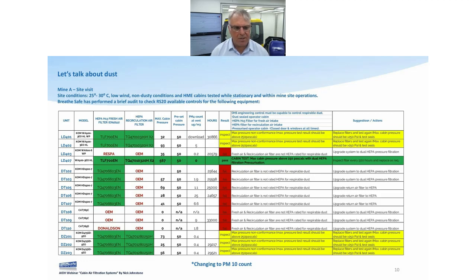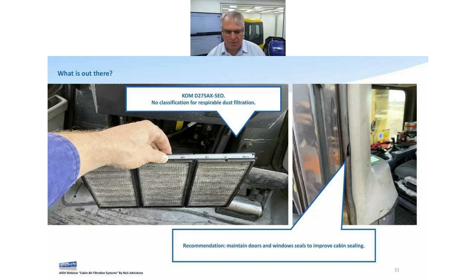The fourth line down in our audit table is essentially where we're targeting for RS20: HEPA fresh air pressurizer, HEPA return air filter, cabin pressure over 300 pascals at full speed, a preset of 50 pascals, and PM count practically zero — measured in micrograms per cubic meter. Once the machine is started and vibrating, it won't be exactly zero, but that green line is exactly where we're aiming. Some products don't have everything needed for RS20.